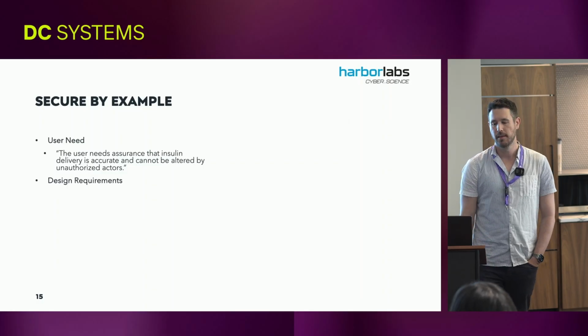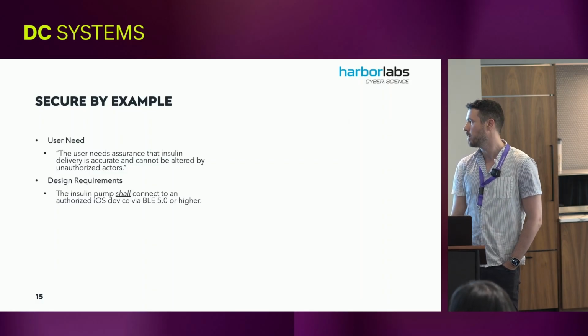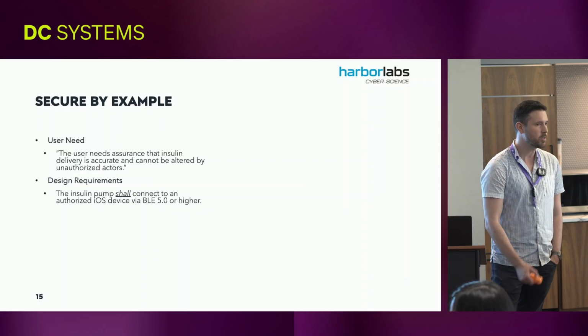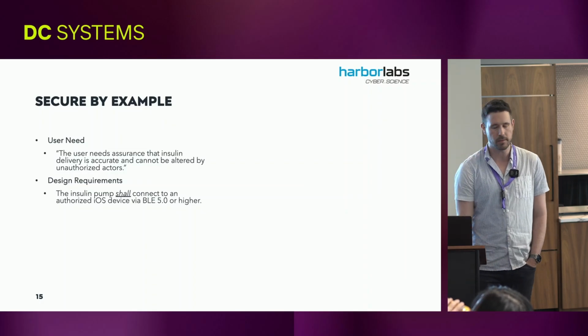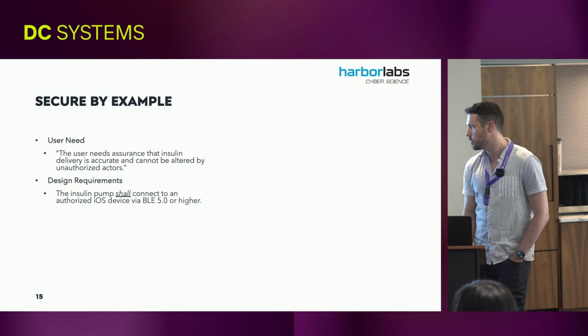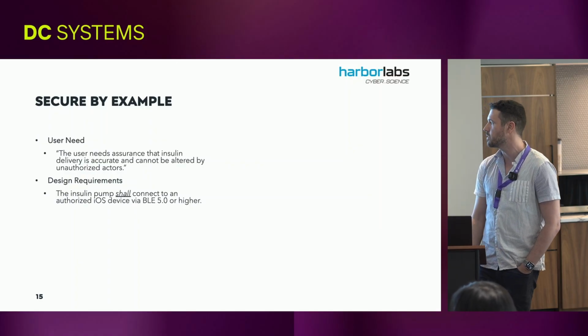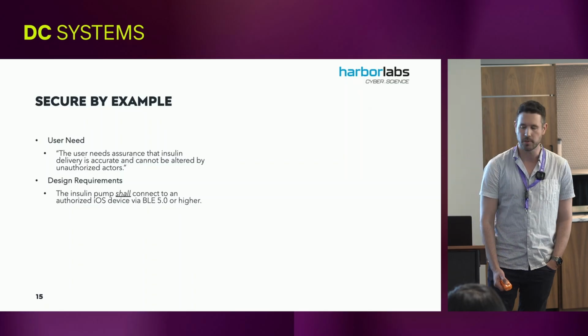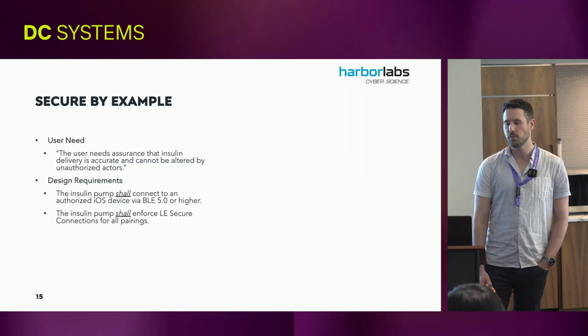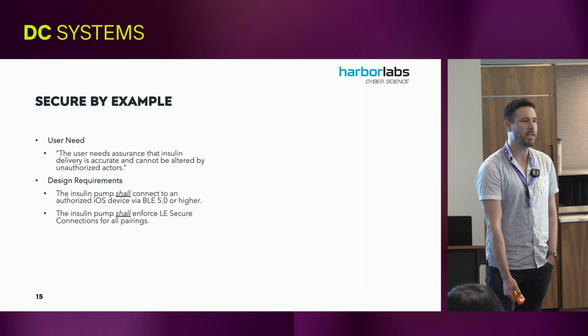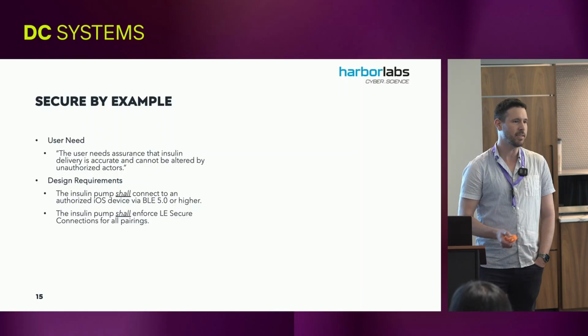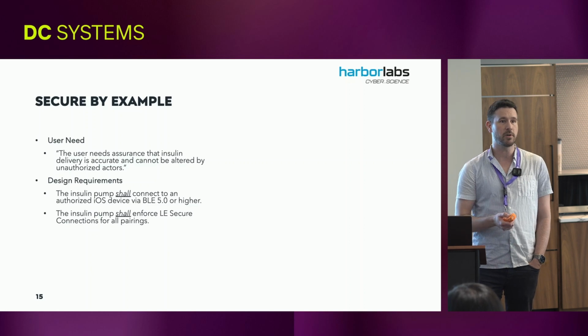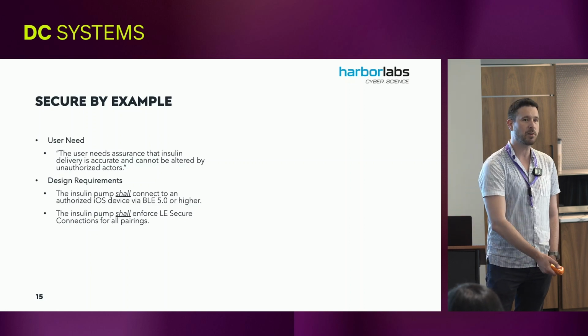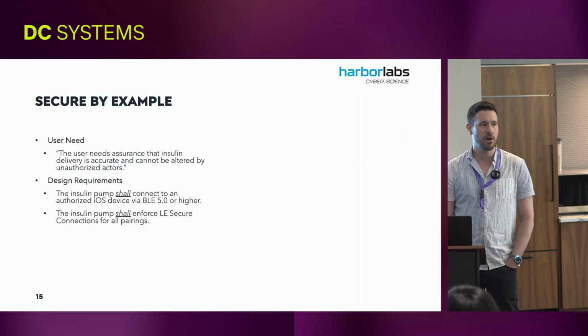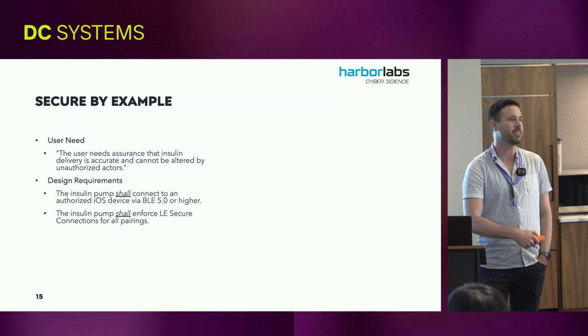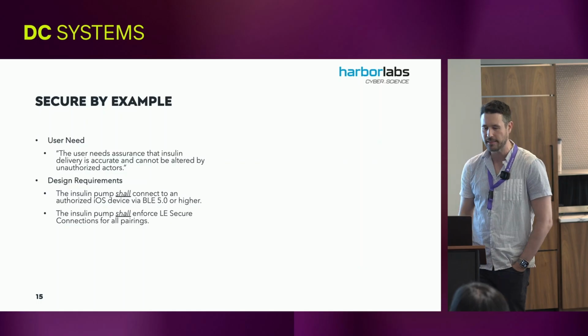Seems pretty reasonable. We would have design requirements, and these could be system requirements or software requirements. It really depends on how y'all go about developing your products. But the insulin pump shall connect to authorized iOS devices via BLE 5.0 or higher. The pump shall enforce LE secure connections. If you don't know the difference between LE secure connections and legacy pairing, you should definitely check it out, because lots of folks use the Nordic nRF SDK and the default code they found on the internet. They come to me and I go, whoa, that crypto's not good. It's easily man-in-the-middle, something to keep in mind.